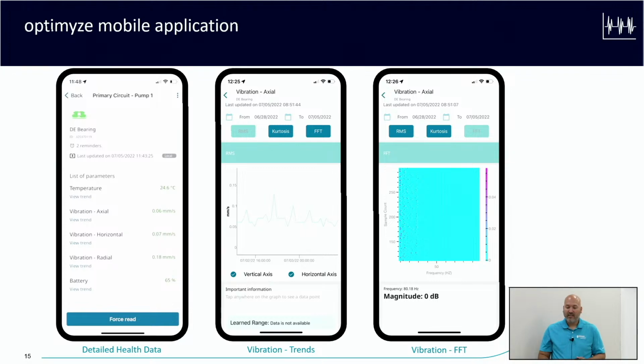And then lastly, the last screenshot there, we have the ability to look at it in FFT chart. Basically, that's just doing a vibration count in the frequency domain. So if you're seeing kind of a heat map or excessive purple dots in, let's say, the first harmonics or 60 hertz, or second harmonics, which is 120 hertz, that could be an indicator of a bent shaft or cavitation, so it can pinpoint and give you an idea of a specific issue that's happening.